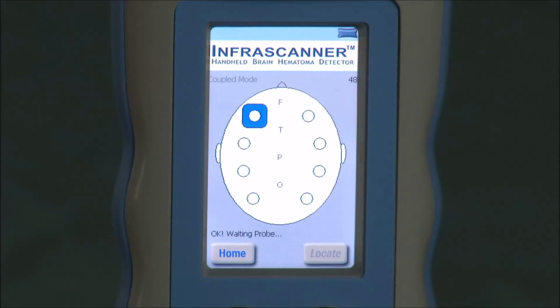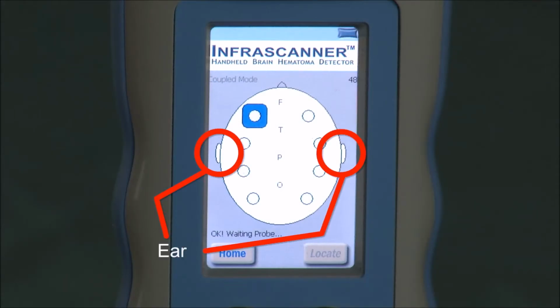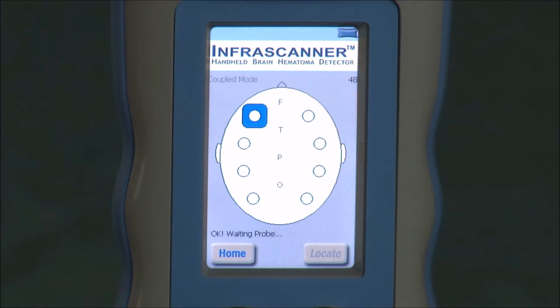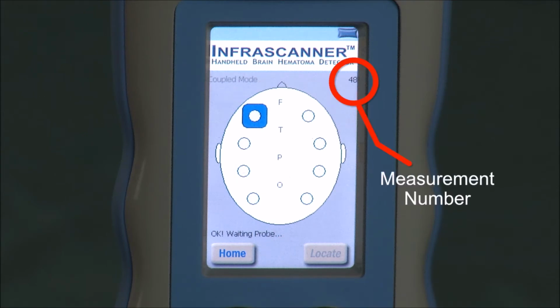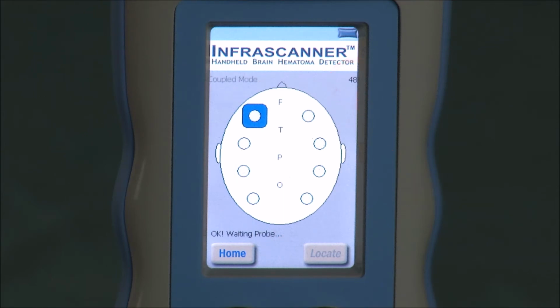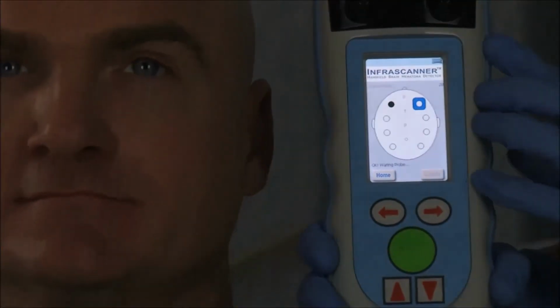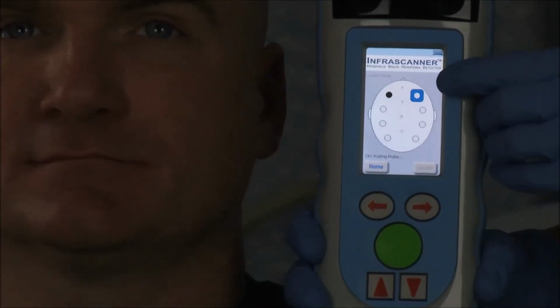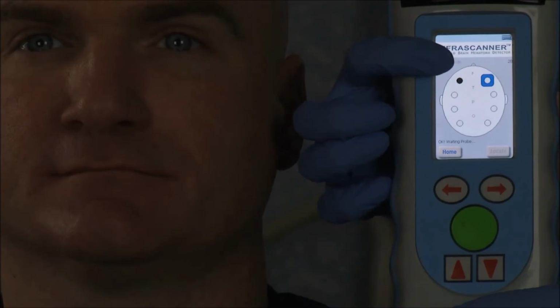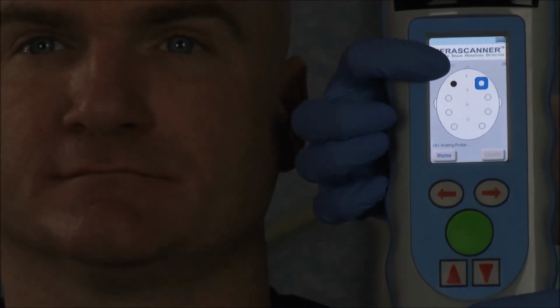The measurement screen shows a diagram of the top of the head. Notice the location of the ears and nose to help with the left-right pattern sequence. Under the infrascanner logo in the upper right is the measurement number. These screen messages tell the operator that the infrascanner is ready to scan. When taking a measurement of the patient, the blue square will always tell you where the next scan should be taken, and the black dot indicates where the measurement has been completed.